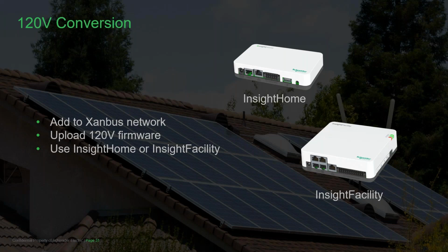Next, add InsightHome or InsightFacility to the Xanbus network. These devices are powered by XW Pro, so make sure the battery breaker is turned on for at least one inverter. InsightHome should be okay for a 3-phase system that is AC coupled. For a DC coupled system with more than 3 MPPT controllers, consider using InsightFacility, which has 2 Xanbus networks.